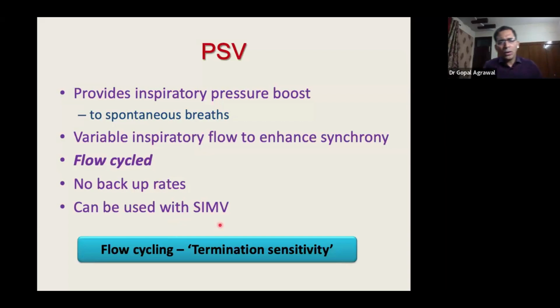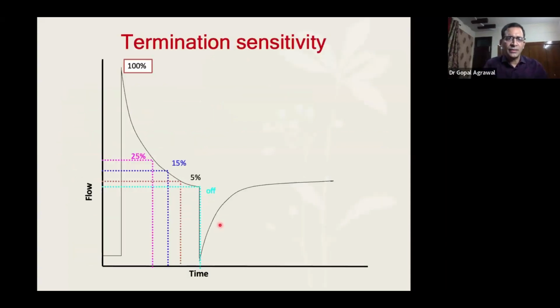And to ensure flow cycling, there's something called termination sensitivity. Let's see what termination sensitivity is. Suppose the peak flow rate is 10 liters per minute. We set the termination sensitivity. Suppose I set the termination sensitivity at 15%. Once the flow is declining and it reaches 15% of peak flow, suppose peak flow is 10 liters, once it reaches 1.5 liters, it will go into exhalation mode.